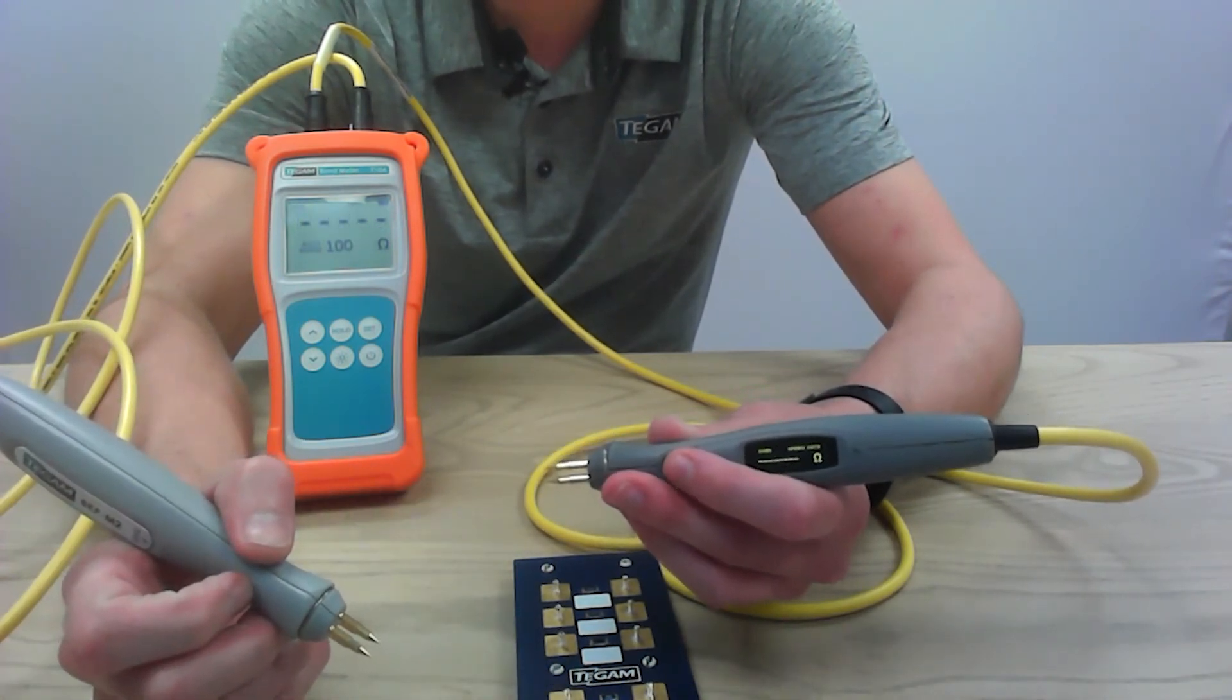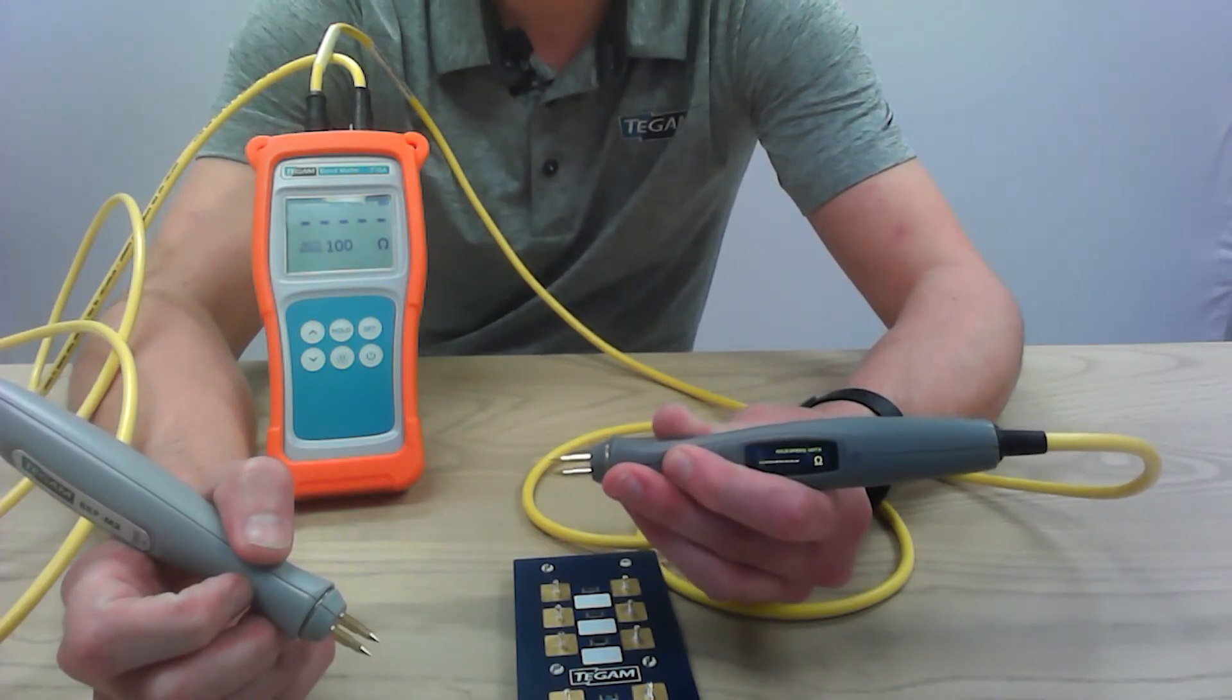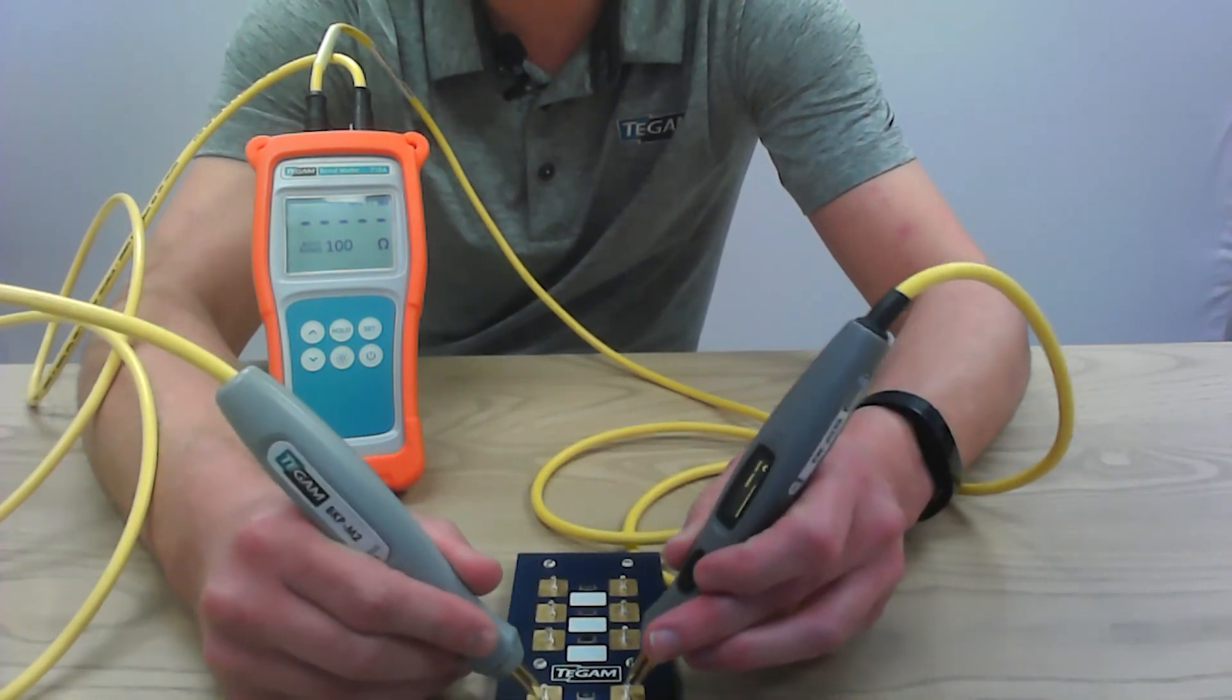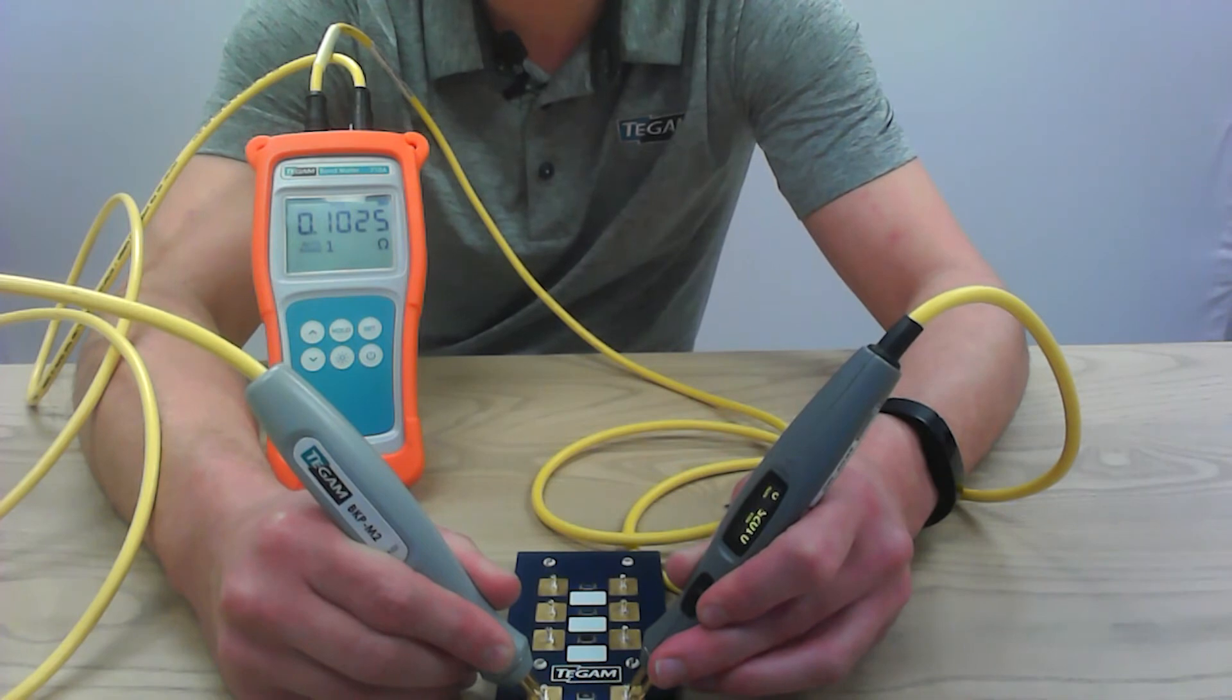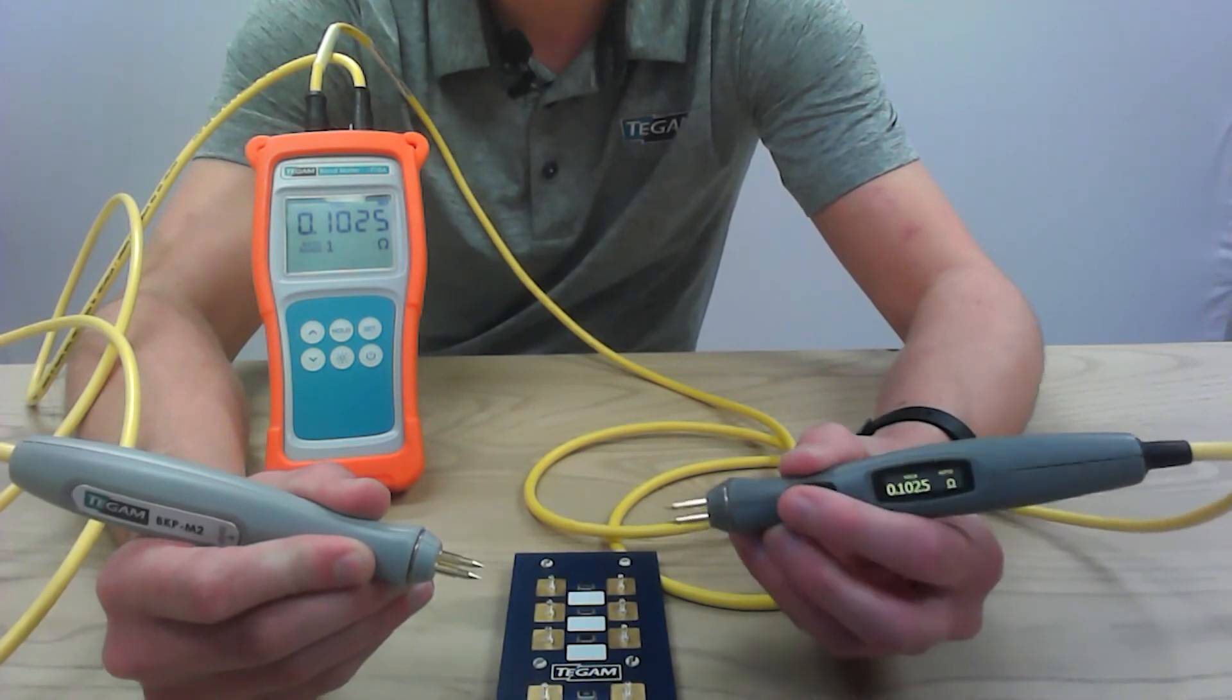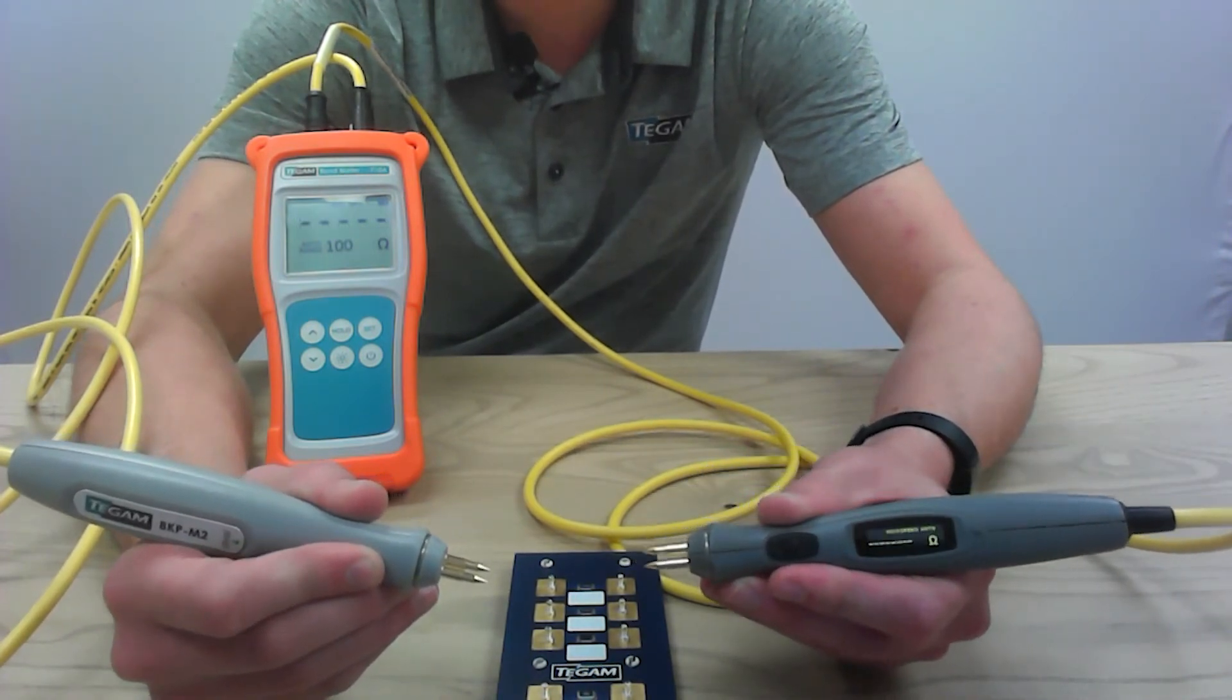To use the 710A's auto hold feature, hold down the button. The hold button will begin to flash, and now you can take your measurement. It will determine a stable reading. Once you get the stable reading, it is automatically held until you press the button again to get it ready for another reading.